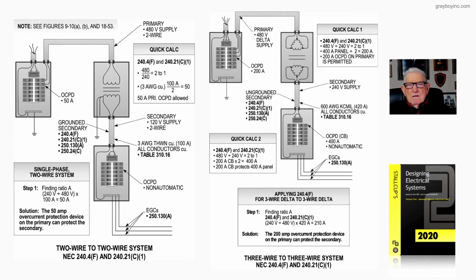Now notice we could use a number 3 THWN copper conductor rated at 100 amps from table 310.16 and the 75-degree column there that we would review. But notice the quick calc, you can also see what we were relating to you to the left of the transformer down at the bottom where it says single phase 2 wire. Then notice it's 240 divided by 480 times 100 would give you 50 amps. It's easier to me to use the ratio, and electricians have told me the same thing. Now, equipment grounds, you could look at 250.130A and 250.122 to size the equipment grounds.